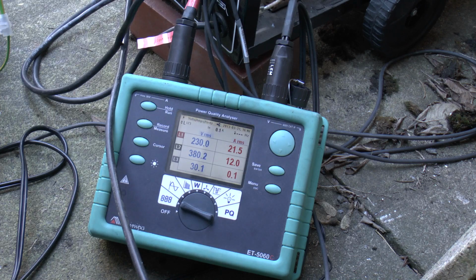Well, if you've seen one of my other videos where I did a bucking transformer, which was stepping 3 kilowatts of power down from 240 to 220 just using a 225 watt toroidal transformer, you may get an idea of why it's working. What we're doing here is the transformer isn't kicking out 415 volts. The transformer is kicking out about 170. But we're just then adding that to the 230 volts, 240 volts coming in to get our output voltage.